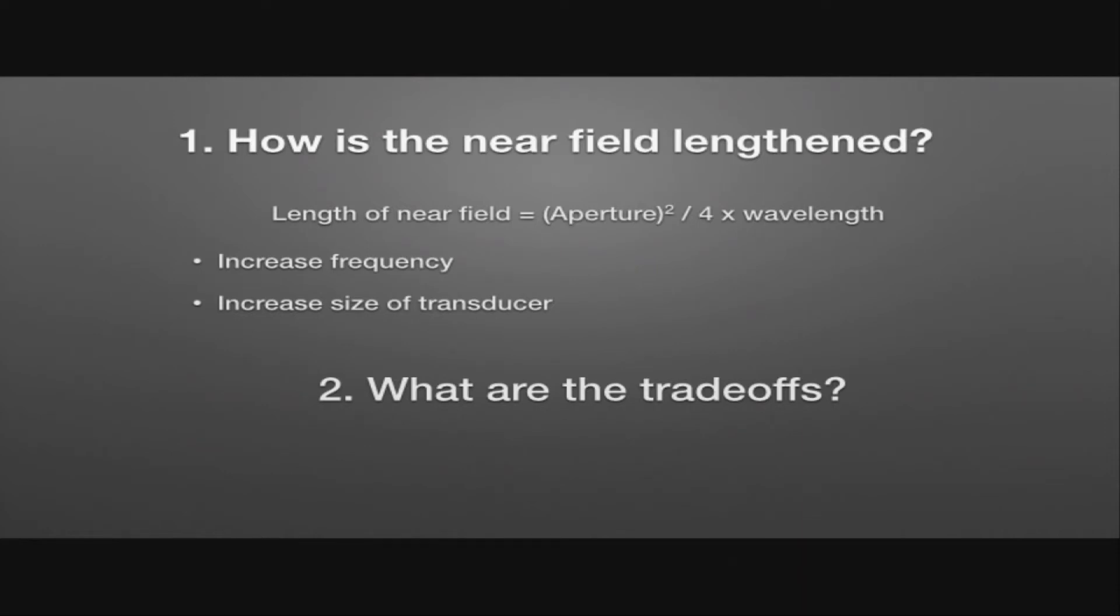Well, I hope you'll now start to have that knee-jerk reaction that whenever anyone says increased frequency, we know that we are reducing our penetration because of increased attenuation. If we increase the size of the transducer, it makes sense, especially if you think of something like echocardiography, for example, we've only got a limited amount of space to try and get in between the ribs, and so we're going to have to limit the size of our transducer to a certain extent.